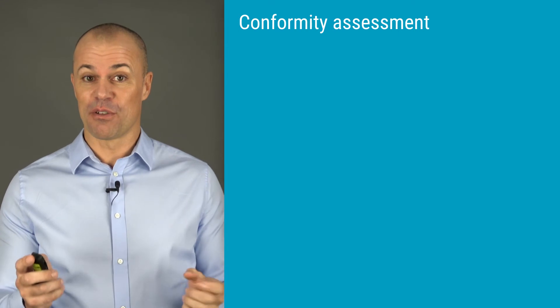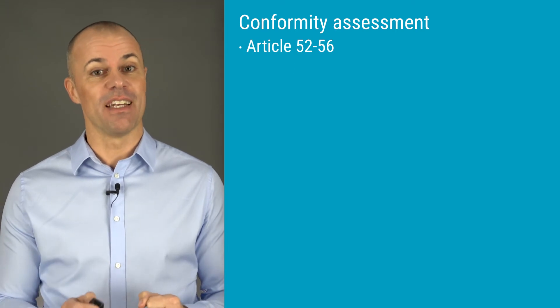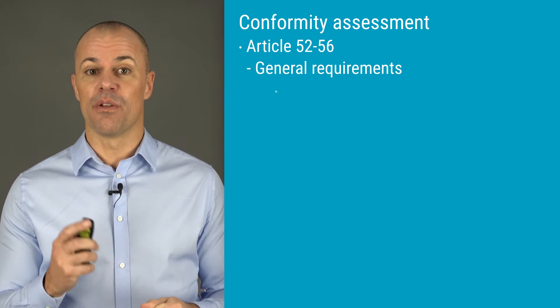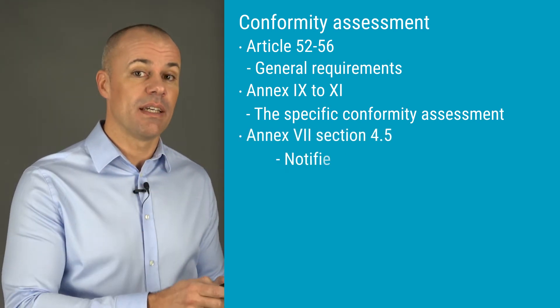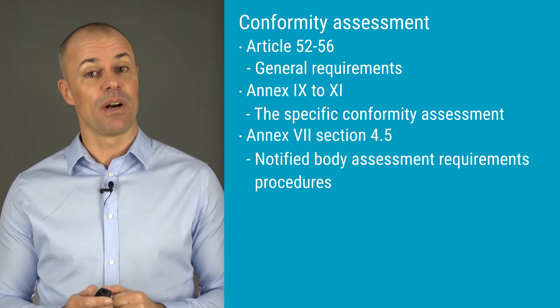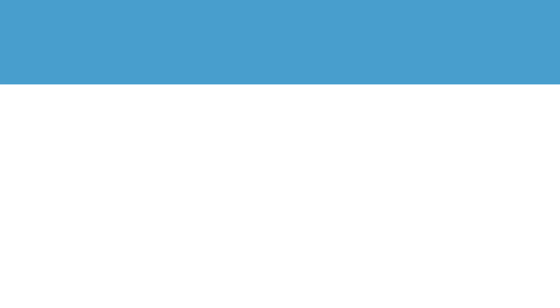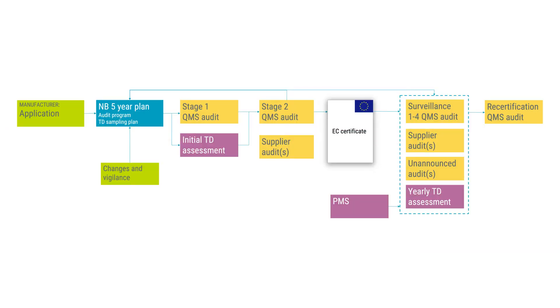The MDR requirements for notified body conformity assessments are a bit spread out in the MDR. The basis is found in Article 52, with references to the three different conformity assessment procedure annexes: 9, 10, and 11. How the conformity assessment is actually done is best described in the notified body annex, Annex 7, under section 4.5. The normal conformity assessment cycle is 5 years and such a cycle can be illustrated like this.